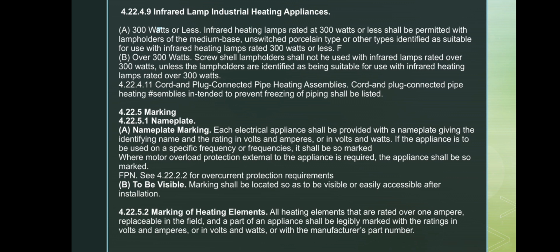Next are the rules for infrared lamps, pipe heating assemblies, and appliance marking. Lamps 300 watts or below may use medium base and unswitched porcelain lamp holders, or any lamp holder approved for lamps of that rating. For lamps over 300 watts, regular screw lamp holders cannot be used unless they are specifically identified as suitable for high wattage infrared lamps.